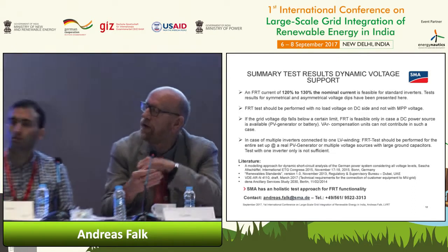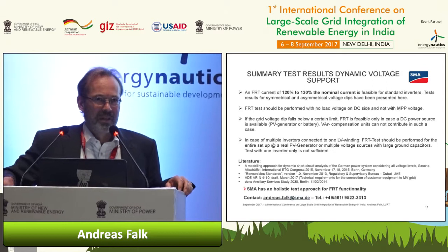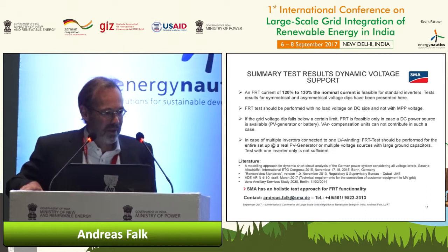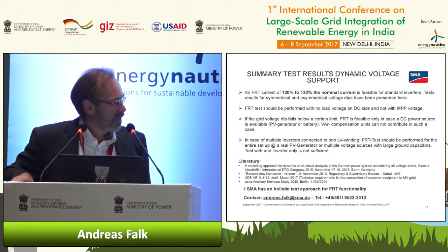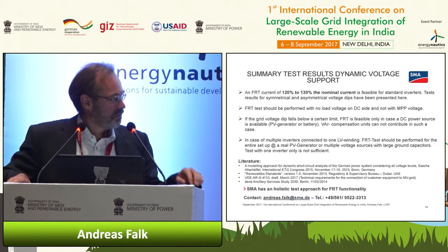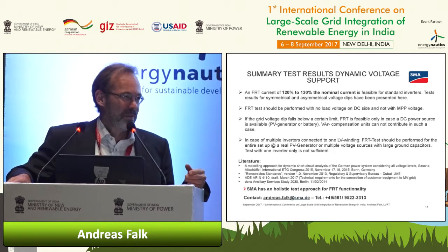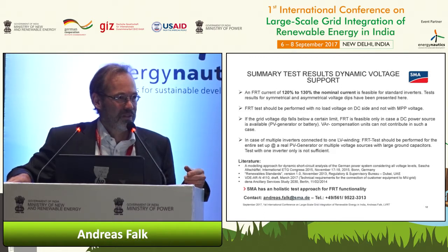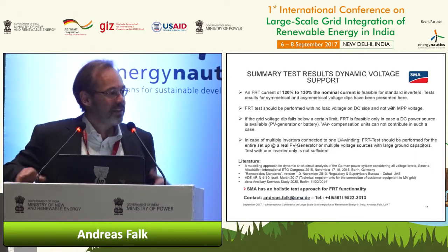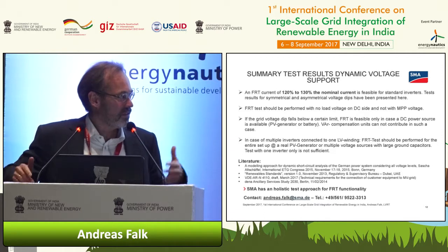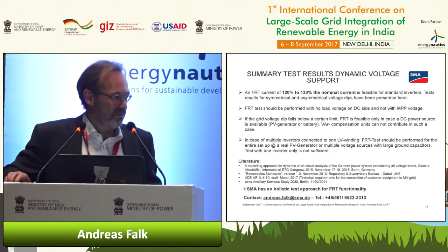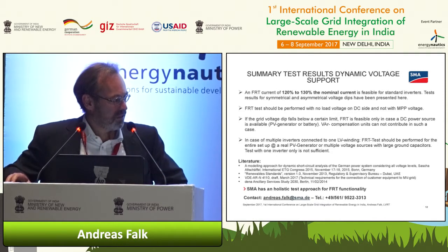Yeah, it is possible to engineer them in that way. It hadn't been done up to now. But when the standards require it, then it is possible. From the semiconductors' point of view, there should be enough reserve in most cases to do so. In case the dip is not too long, in case it is somewhat 300 milliseconds, then it is feasible. For seconds, it's not that easy.